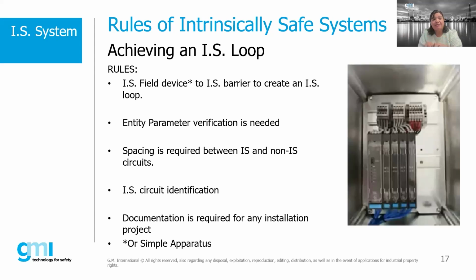Lastly, a very important rule for intrinsic safety is documentation. Once you do the matching - you select your IS field device, your IS barrier, you do the entity parameter verification - just have it on file, and it needs to go to whoever has that system, to confirm the installation is done properly. In 5, 10, 15 years, when you need to do maintenance, updates or replacements, you can go into that document and see what's allowed under those rules for installation.